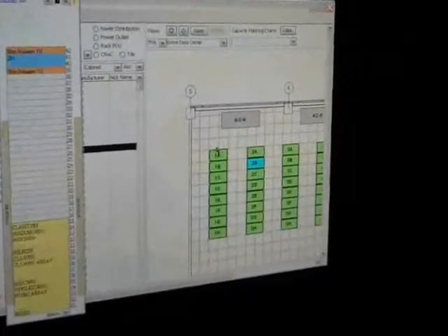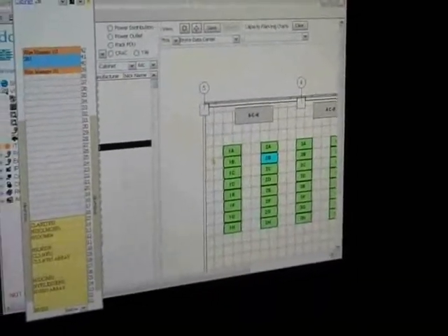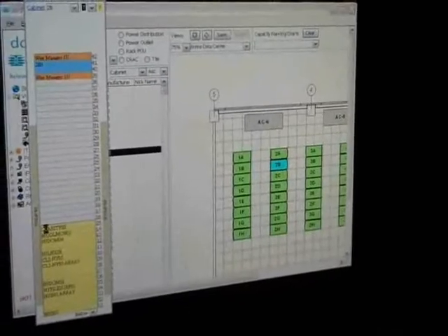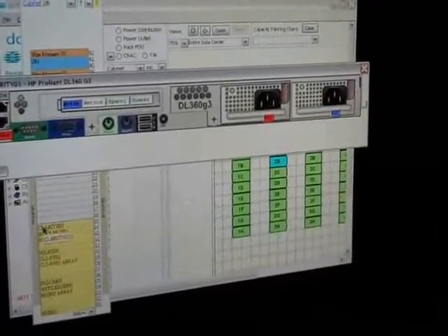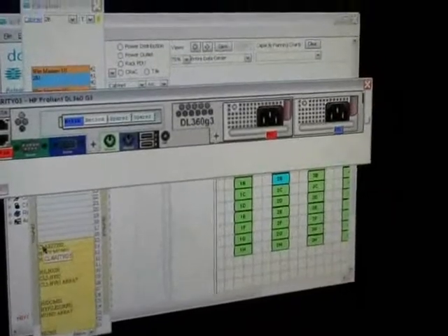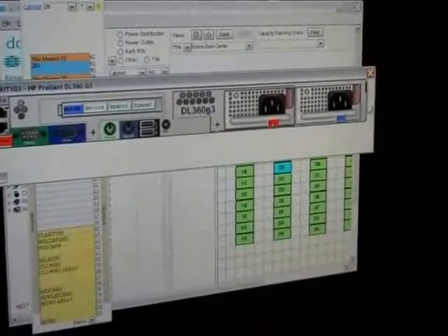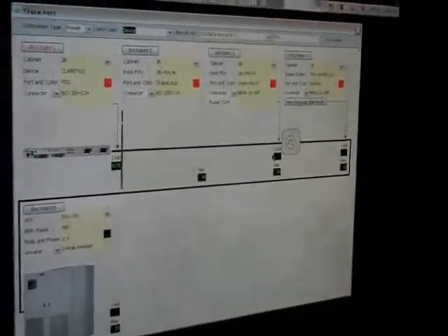When I mentioned about the interdependencies, what we're talking about is taking every single element — whether it be a power supply, a network port, or a communication port — and being able to interrelate that via hyperlink back to the individual components it's connected to. In this situation, we have an individual power supply on a server, connected to an outlet on a Raritan smart PDU, connected to a circuit and panel positions back in the RPP.